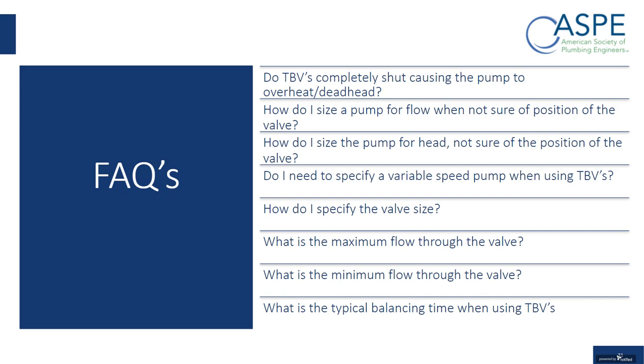The minimum flow through a thermostatic valve can actually, in theory, be 0 because these valves are self-actuated. You can put a thermostatic valve in a cup of hot water as high as or higher than whatever your return temperature is in that valve, and it will close. If you put it in cold water, it will open. So there's no pressure drop across the valve. There's no flow through the valve, and it still operates, opens, and closes.